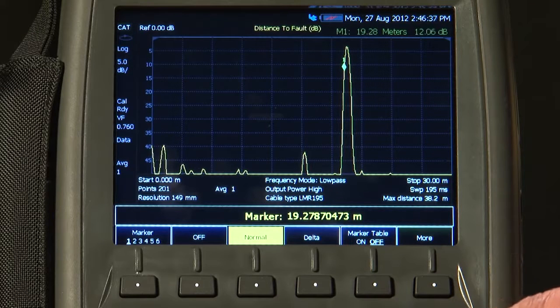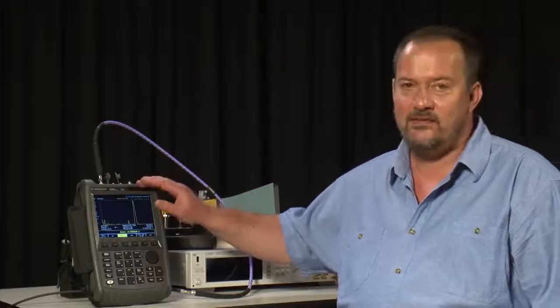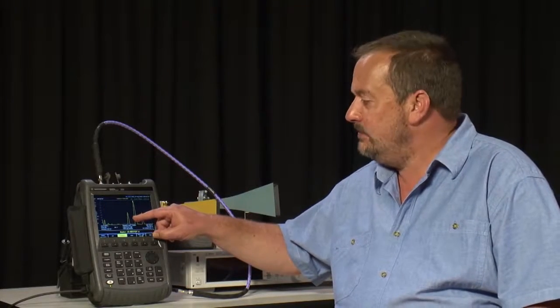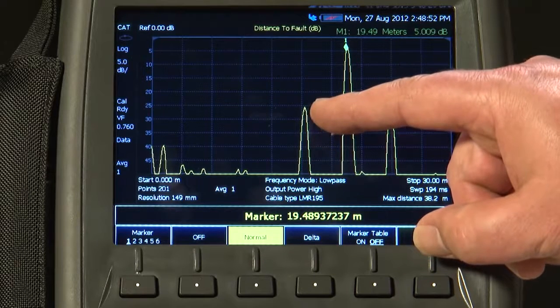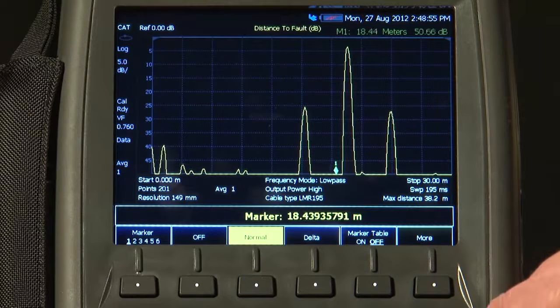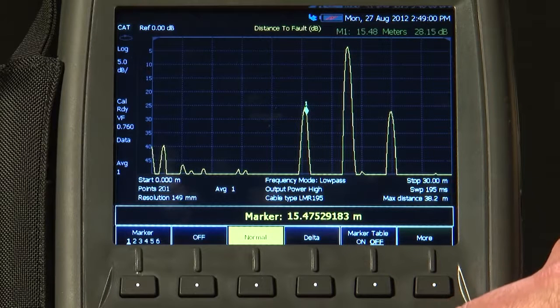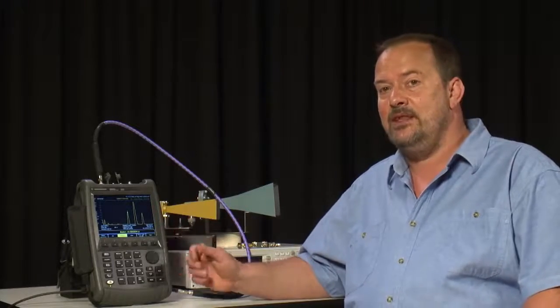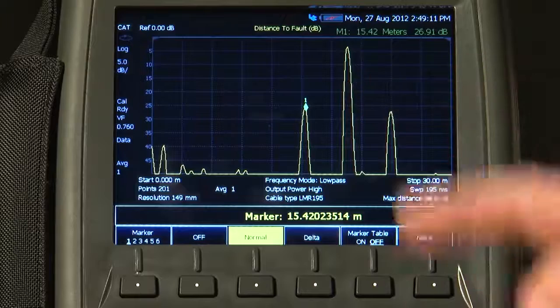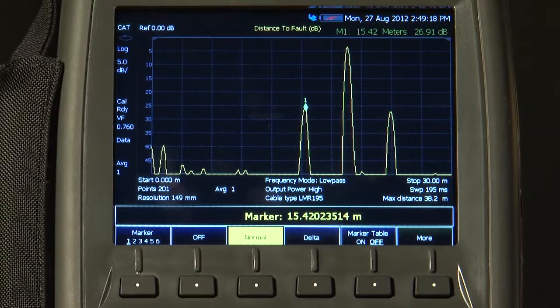So you can see here that the antenna is 19.44 meters from the FieldFox. I have now replaced what was a good quality bulkhead connector with a cheap adapter. And you can see immediately now that the response of that has increased significantly. And in fact, if we put the marker on there, you will see that we have a return loss of 26.9 dB. Now, that may be acceptable in your setup. And in any case, it at least shows a sign of perhaps degradation. Maybe it needs to be fixed next time you are out on site.